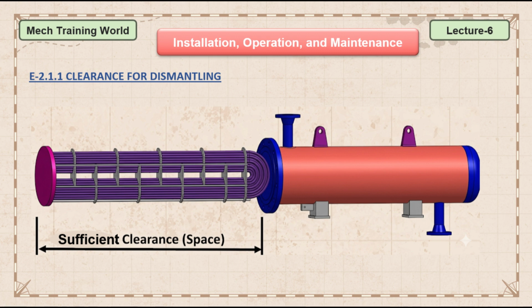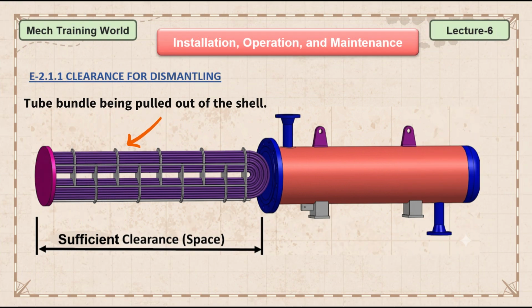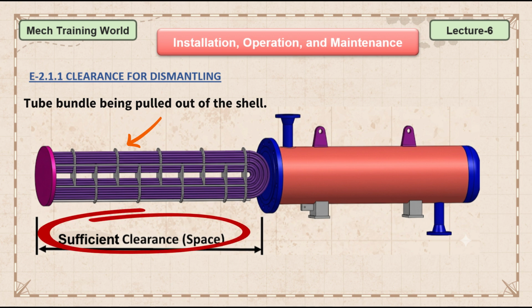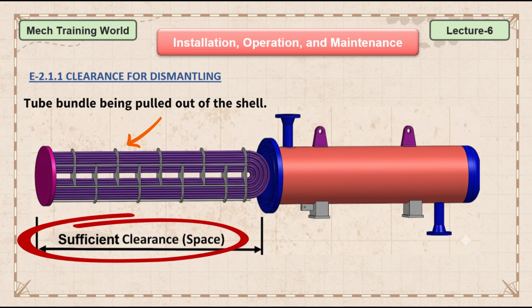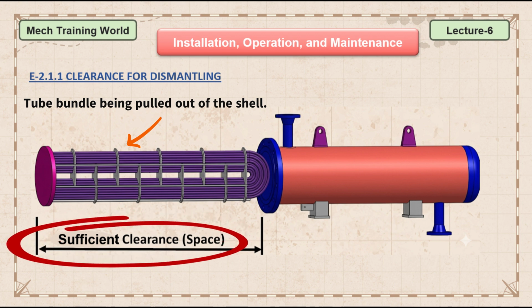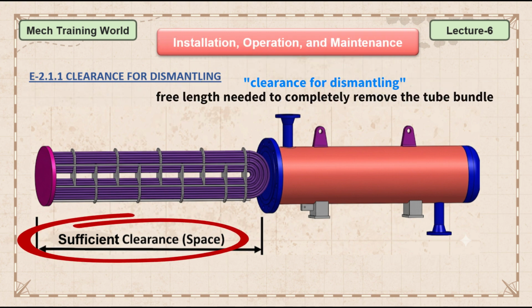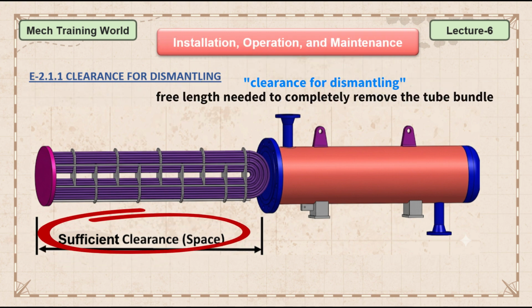Let's start with clearance for dismantling, which is mentioned in E 2.1.1. Take a look at this figure. You can see the tube bundle being pulled out of the shell. Now here's the key point: this cannot happen unless sufficient space is provided during installation. This required space is called clearance for dismantling. It is the free length needed to completely remove the tube bundle for inspection, cleaning, or repair.